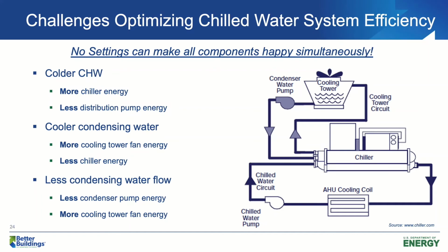The water side is a little bit more complex because there's no settings that can make all components work as efficiently as possible at the same time. For example, if we make colder chilled water, that means our chillers need to work harder and use more chiller energy. But at the same time, we do not need as much chilled water. That means our pumps will be happier and use less energy. Now you can see the trade-offs between chiller energy and pump energy. All right, if we make cooler condensing water, our cooling tower fans need to work harder. That means more cooling tower fan energy. But on the other hand, the chillers will be happier, more efficient, and use less chiller energy. That is some trade-offs between chiller energy and cooling tower fan energy.